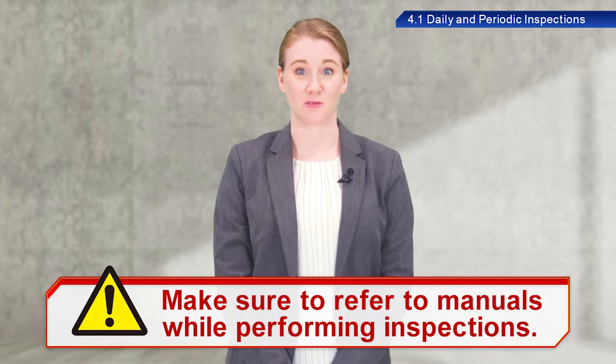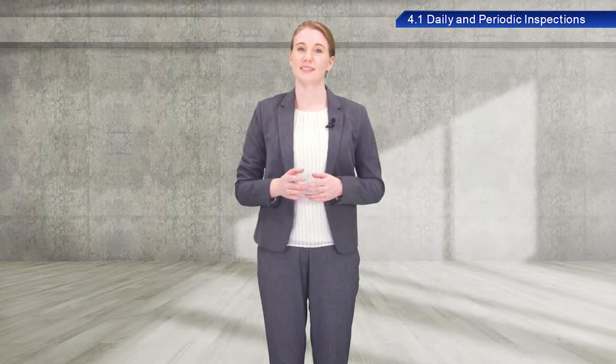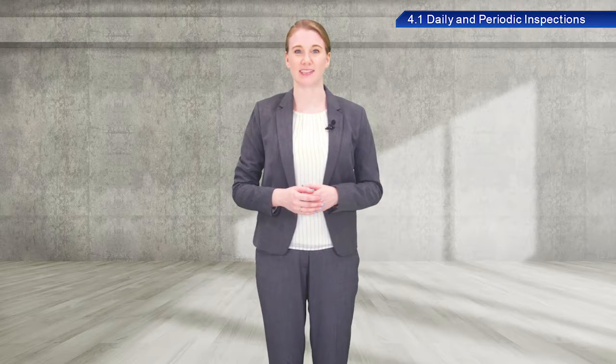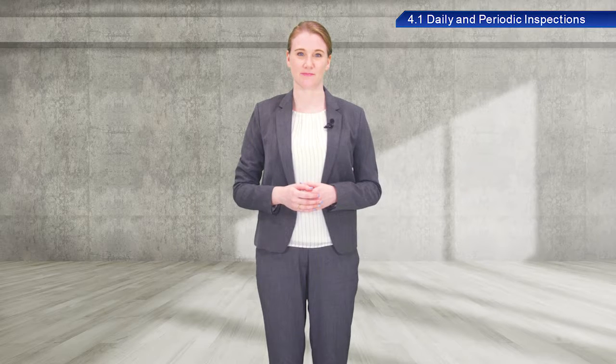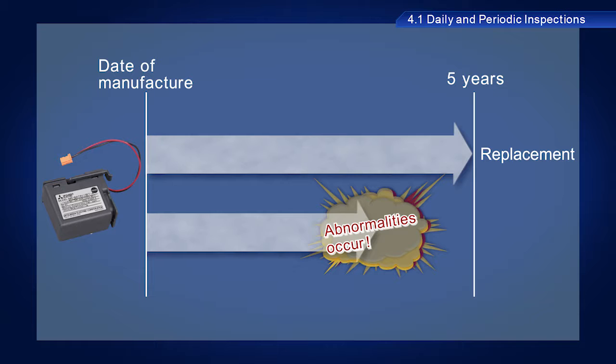Make sure to refer to manuals while performing inspections. Some AC servo parts must be replaced periodically. The battery is one of these parts. Servo amplifiers include a battery to maintain the current position information stored in the encoder memory when the power to the servo amplifier is turned off. Batteries typically last for five years from the date of manufacture but may need to be replaced before then as necessary.